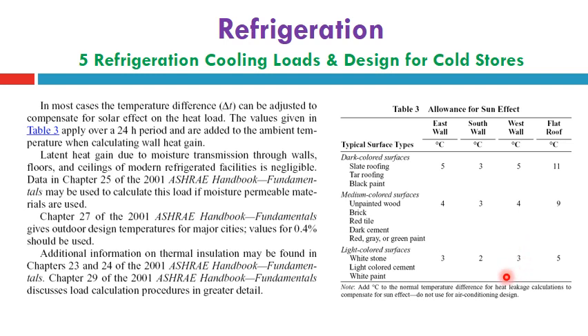If we have a light colored surface for east wall and west wall, we must add this value to the northern wall during the calculation of east and west walls. But for south we add only 2 degrees, and for roof we add 5 degrees additional to the northern wall, when taking into consideration the area of the roof exposed to the sun rays all of the time. So it should be noted that this value for flat roof is always larger than for the east and west walls, and also larger than the south wall, due to the sun's movement.